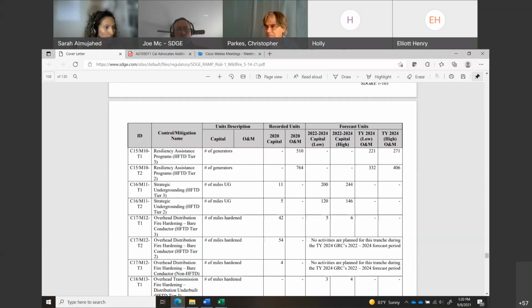This is a remainder of what used to be known as the prime and firm programs. Those programs targeted specific assets deemed at risk based on specific characteristics. For example, in the firm program, we targeted small copper wire known to be more prone to wire down incidents. Based on location in the HFTD and the consequences tied to those locations, we identified a list of conductors to prioritize for replacement. Similarly, for the prime model, we looked at potential pole loading issues and prioritized poles to be replaced across the system. That program has been ongoing for years.